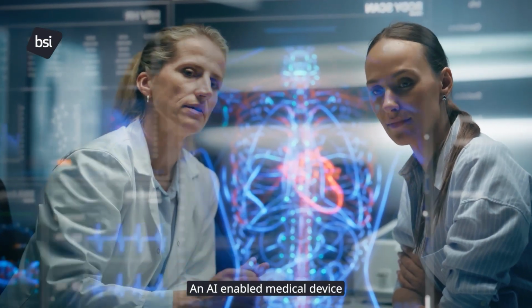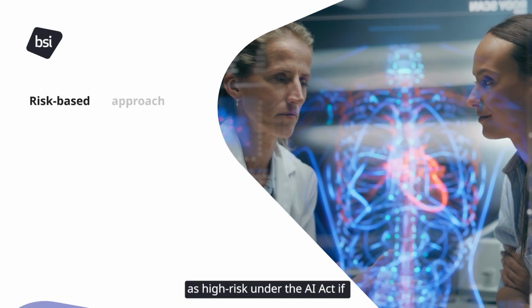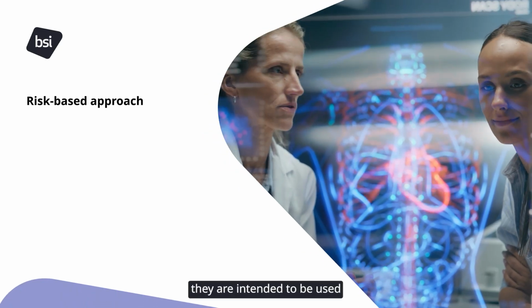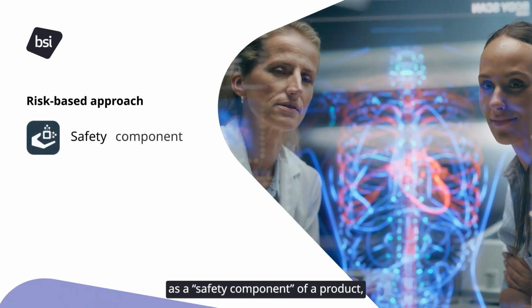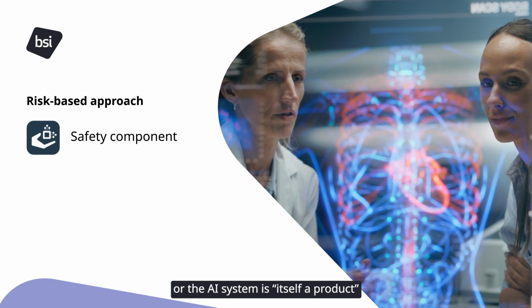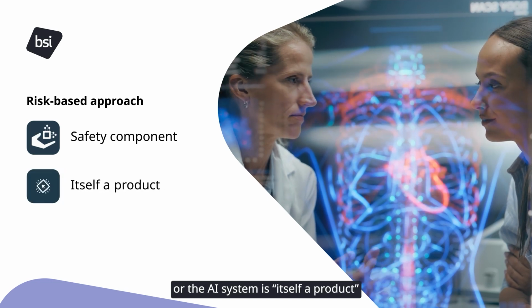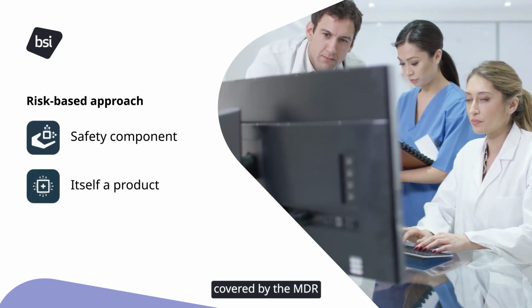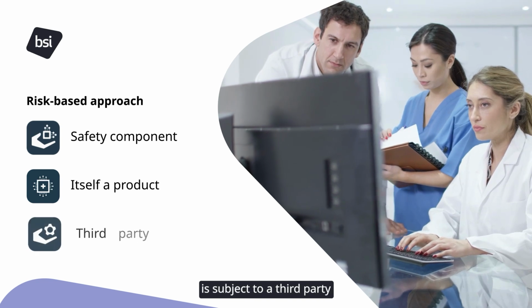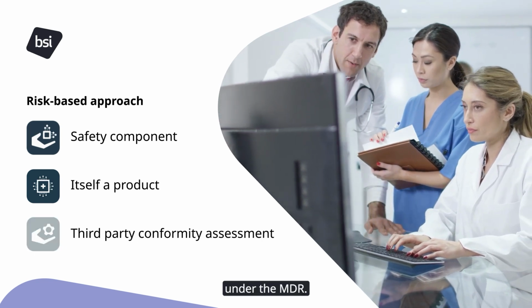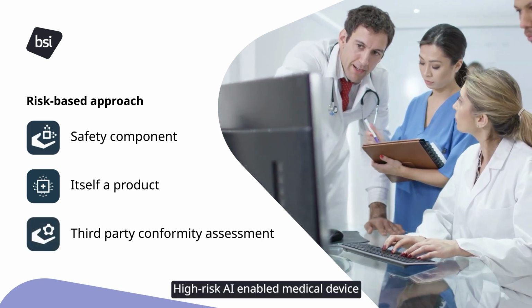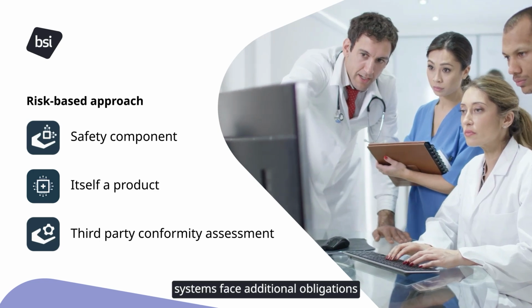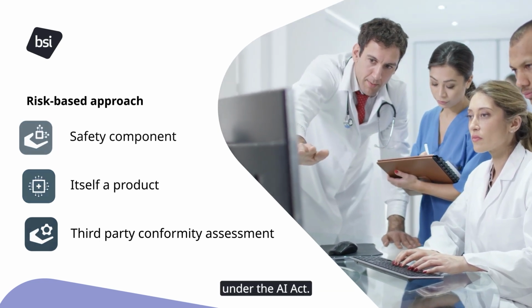An AI-enabled medical device will be classified as high risk under the AI Act if it is intended to be used as a safety component of a product, or the AI system is itself a product covered by the MDR, and such product is subject to third-party conformity assessment under the MDR. High-risk AI-enabled medical device systems face additional obligations under the AI Act.